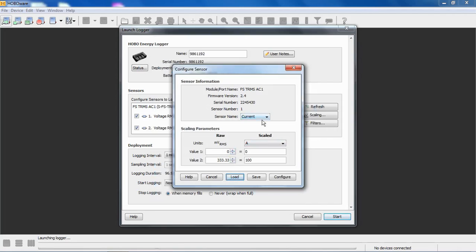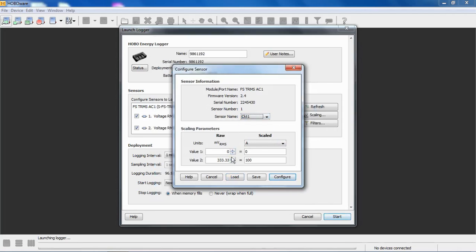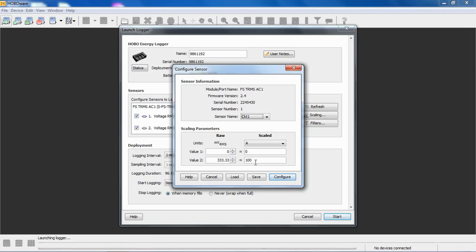It did take out our circuit name, our sensor name, but we can put that back in if we want to. Now we have a relationship set up in here where zero output of that CT equals zero amps, 333.33 millivolts AC output, which is full scale, equals 100. And then our data will be represented by zero to 100 amps rather than zero to 333 millivolts. If you don't scale these TRMS modules, your raw data will just be the voltage output of the transducer, which is typically zero to 333 millivolts.